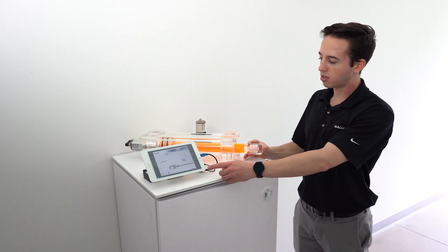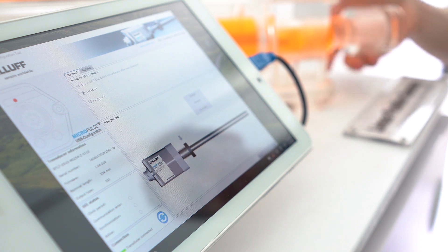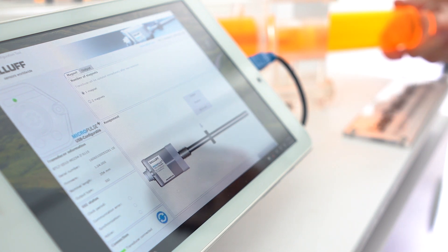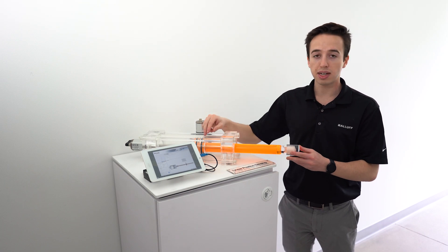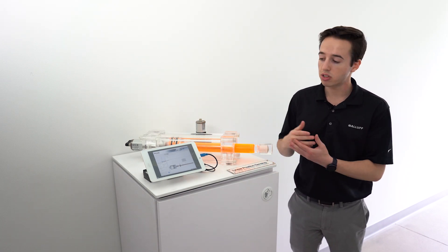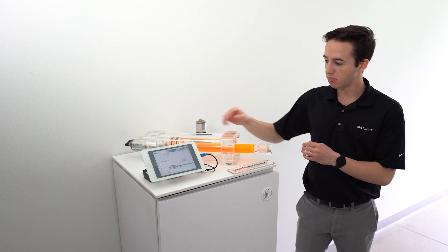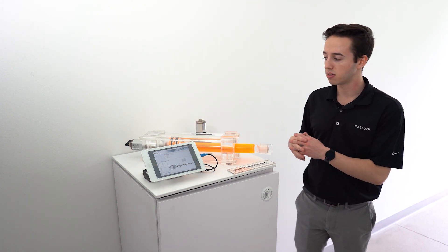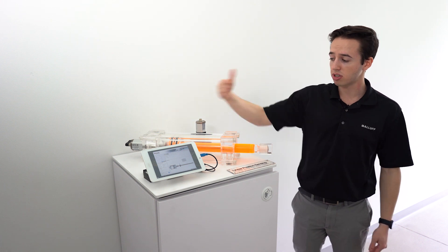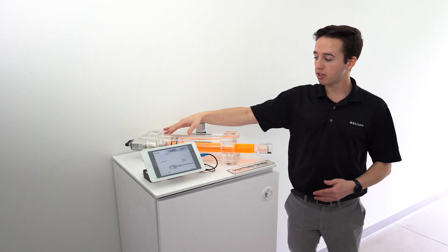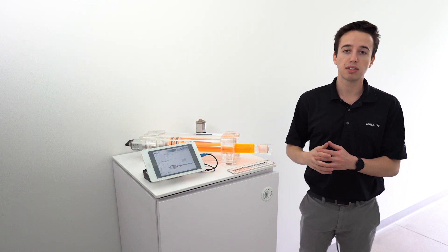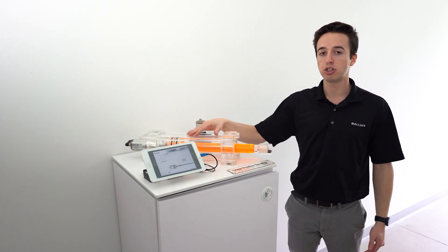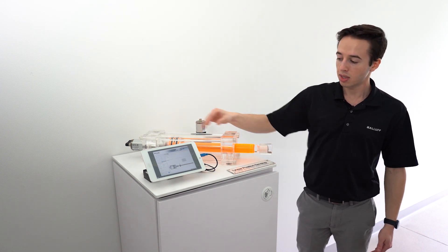So as you can see as I move the cylinder the magnet changes and gives out the position, or if you're using two magnets on an analog current or voltage output model you can have differential position between the two magnets. And actually you can get more magnets if you're using an ethernet or a field bus or IO-Link version; you can have up to 16 magnets allowing you to get up to 32 measurements per BTL.